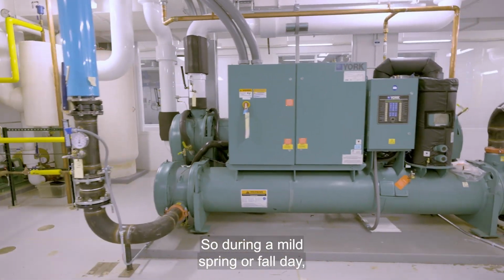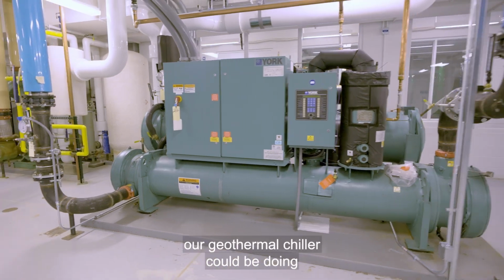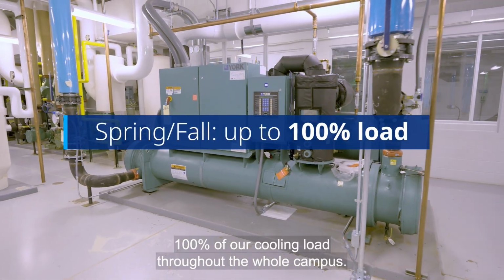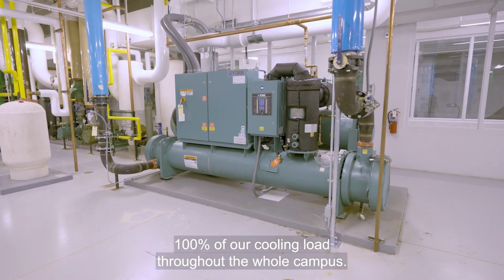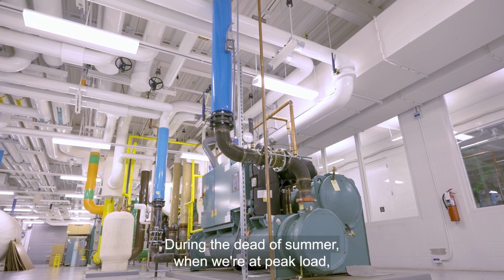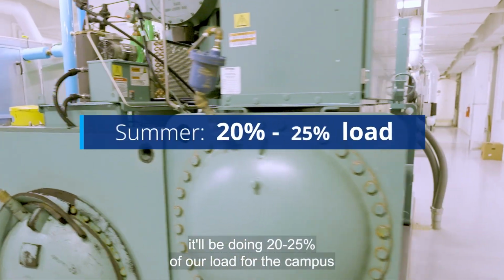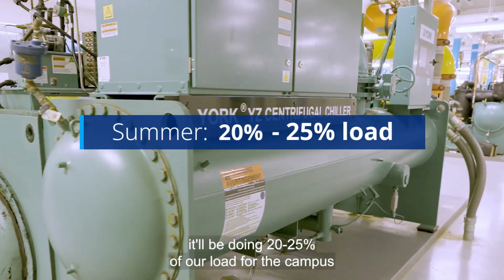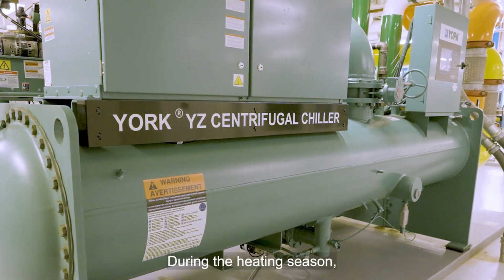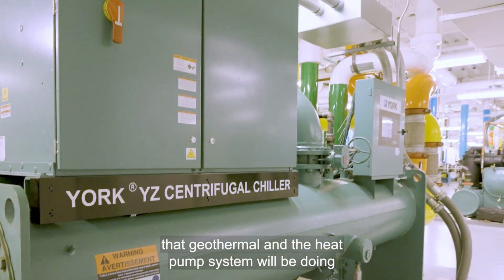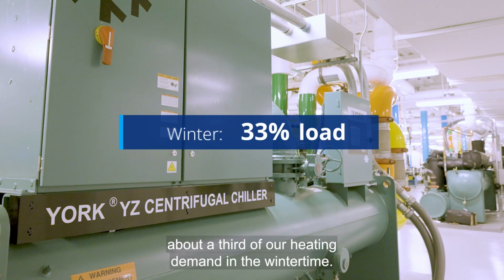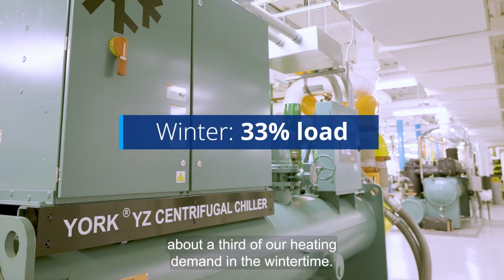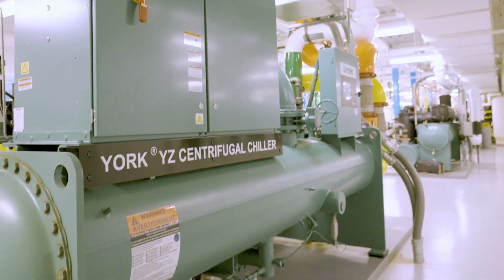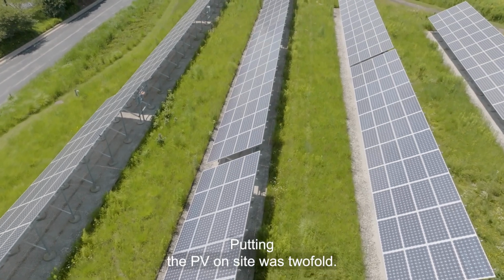So during a mild spring or fall day, our geothermal chiller could be doing 100% of our cooling load throughout the whole campus. During the dead of summer, when we're at kind of peak load, it'll be doing 20-25% of our load for the campus. During the heating season, that geothermal and the heat pump system will be doing about a third of our heating demand in the wintertime. Putting the PV on site was twofold.